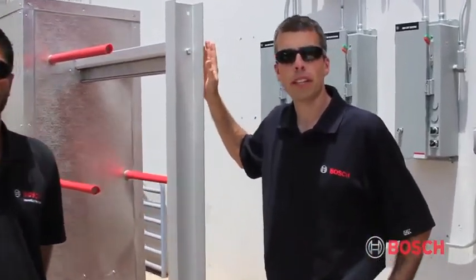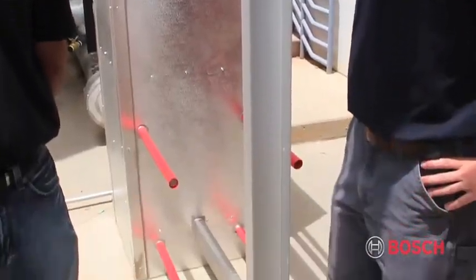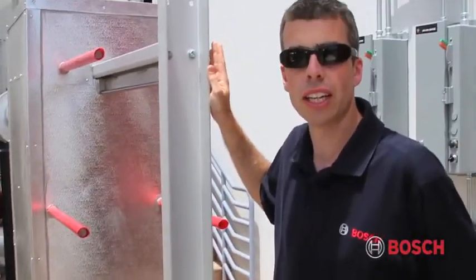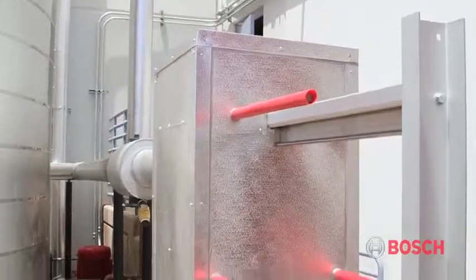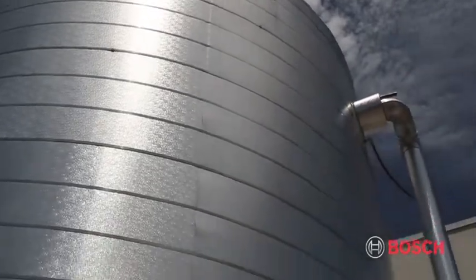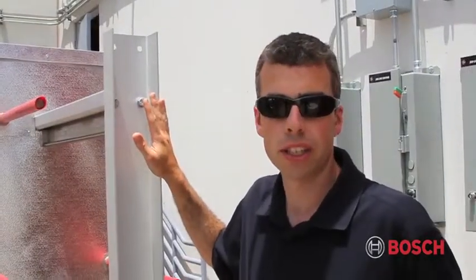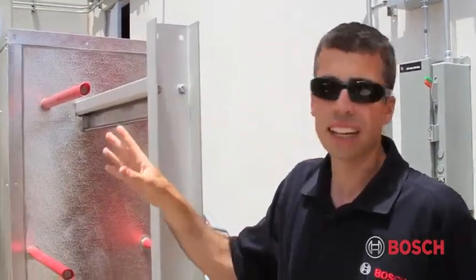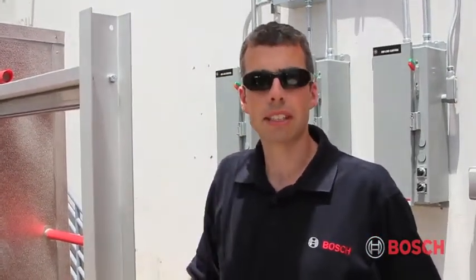What you see here is a commercial grade heat exchanger — there are two of them on this project. The heat transfer fluid circulating through the 880 collectors on the roof is deionized water that has been treated. That water doesn't leave the collector loop. The buffer tank water, which is our storage medium, is also a closed loop separated by two heat exchangers, which stores the thermal energy harvested during the day. That energy is then taken out of the buffer tank through a second heat exchanger and integrated into the domestic hot water system.